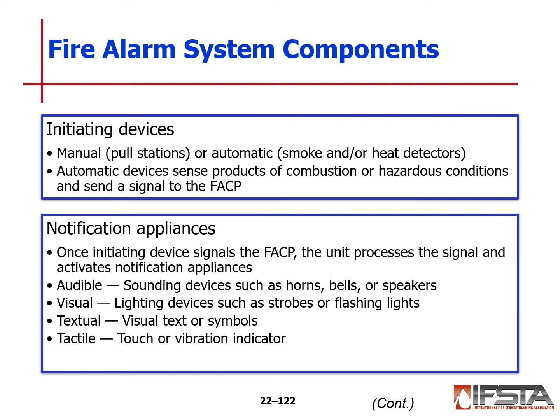Notification appliances: once the initiating device signals the panel, the unit processes the signal and activates the notification appliances. This could be audible or visual alarms. Your audible alarms are sounding devices such as bells, speakers, horns, or sirens. Visual are lighting devices such as strobe lights or flashing lights. Textual is visual text or symbols, and then tactile is touch or vibration type indicators. A lot of your modern fire systems will talk as well.